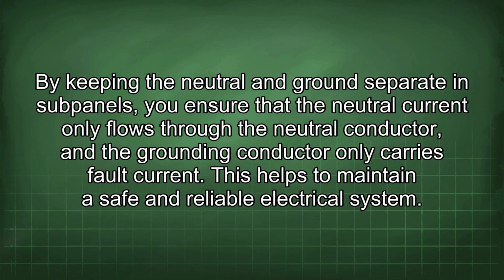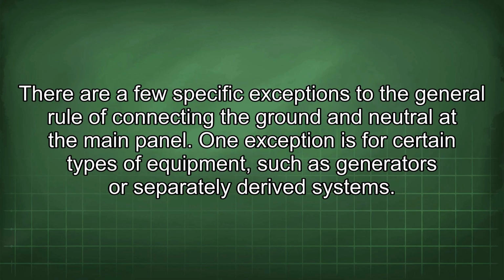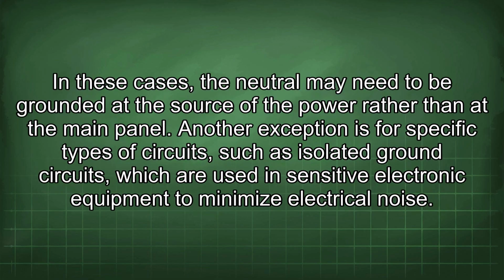This helps to maintain a safe and reliable electrical system. There are a few specific exceptions to the general rule of connecting the ground and neutral at the main panel. One exception is for certain types of equipment, such as generators or separately derived systems.